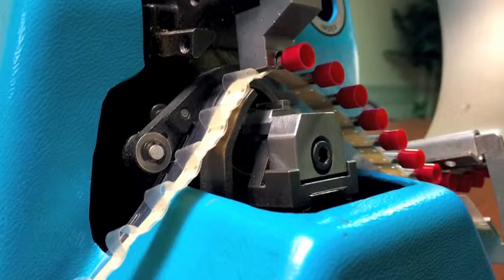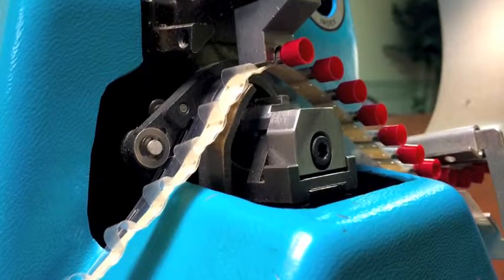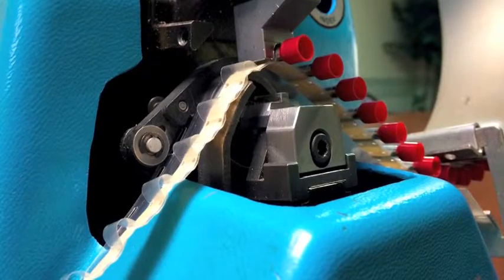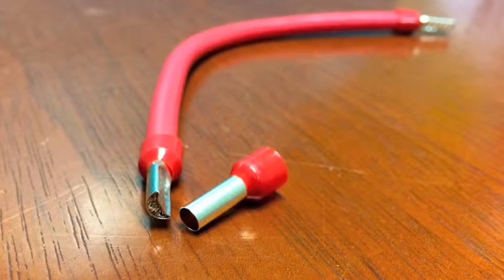The H270 can crimp tape-mounted 26-gauge through 8-gauge ferrules. We have another machine that can crimp up to 4-gauge tape-mounted ferrules. The machine can also be used for crimping twin ferrules.